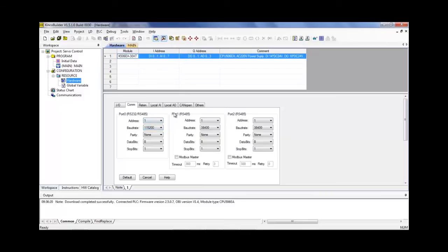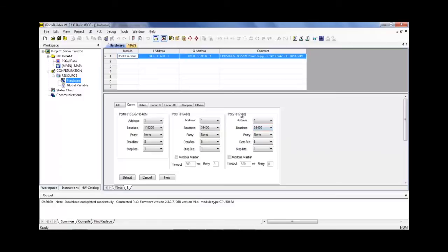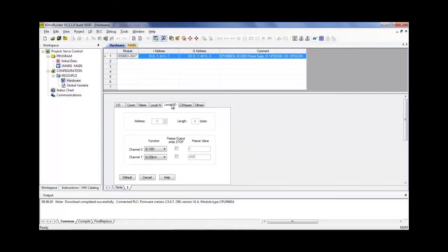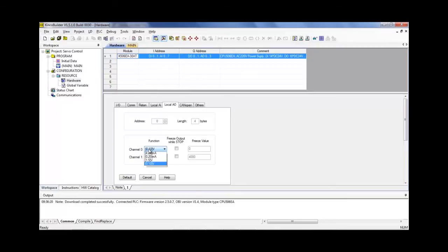Secondly, we have to configure the communication port that the HMI and PLC are talking on. So, like I said, it's two-wire RS-485 at 38,400 using port 2. Lastly, we have to configure the analog output port. So, we'll be using channel 0 and we'll select it to be 0 to 10 volts.